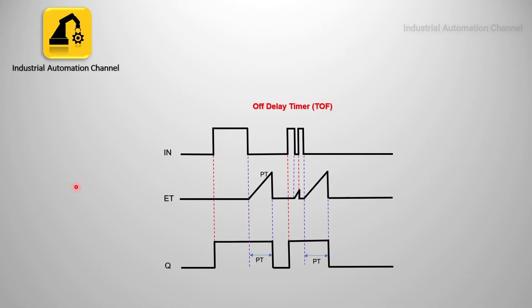Here you see the function diagram for TOF. As soon as you turn on the input, the output turns on. The elapsed time only starts to count when you turn off the input. When the elapsed time reaches the preset time, the output will be turned off. If you turn the input on and off again before the elapsed time reaches the preset time, the elapsed time will be reset.